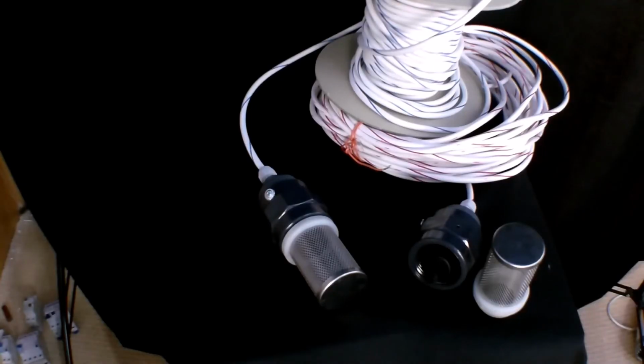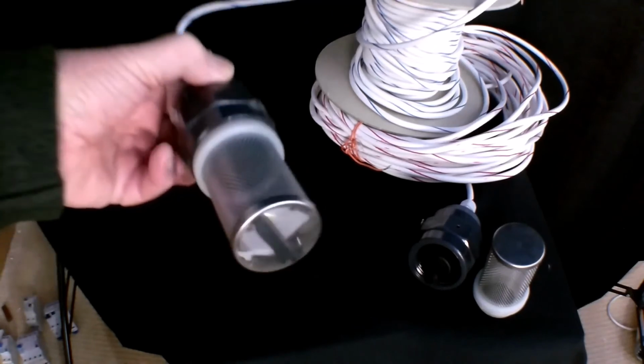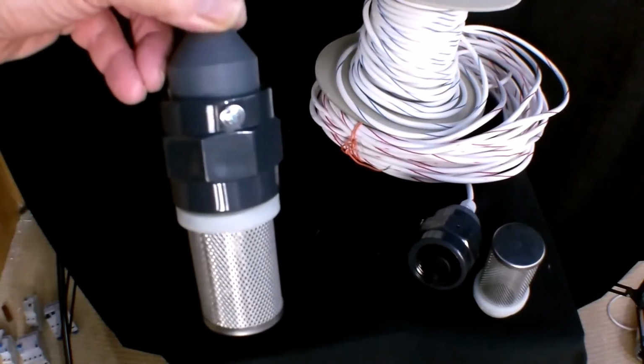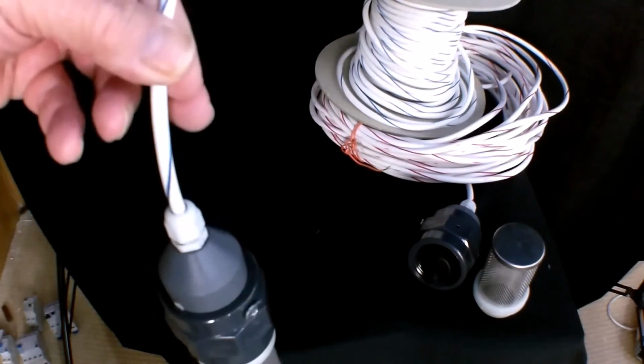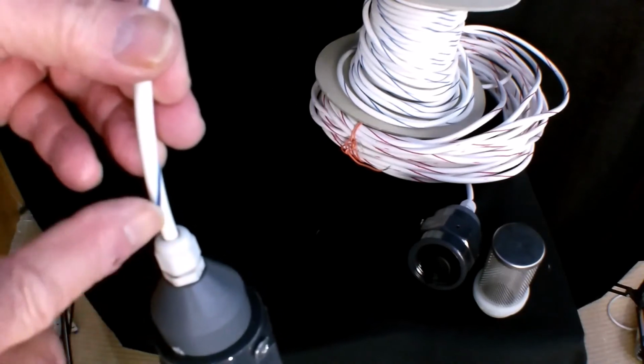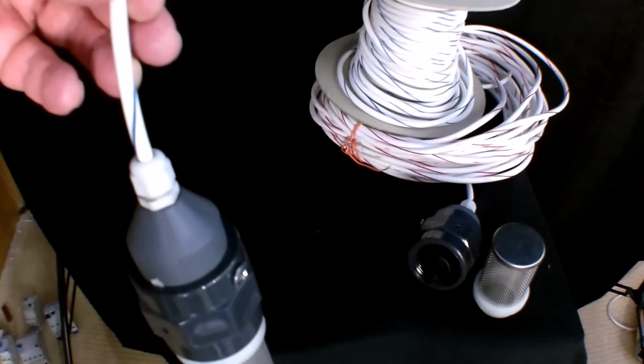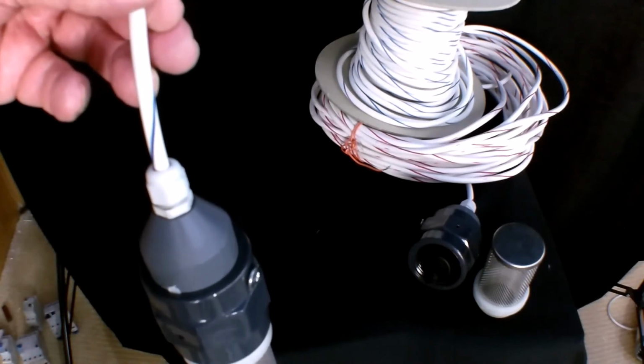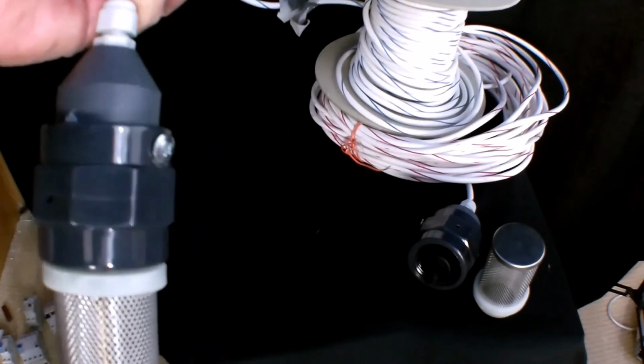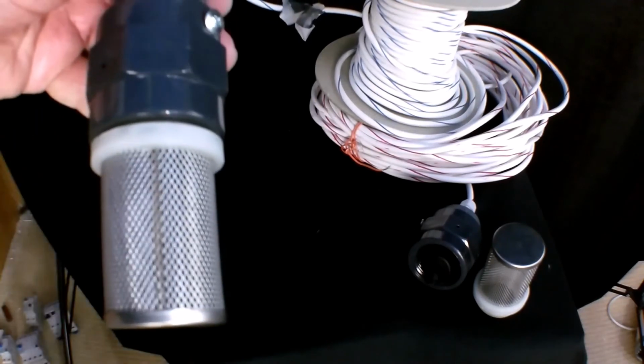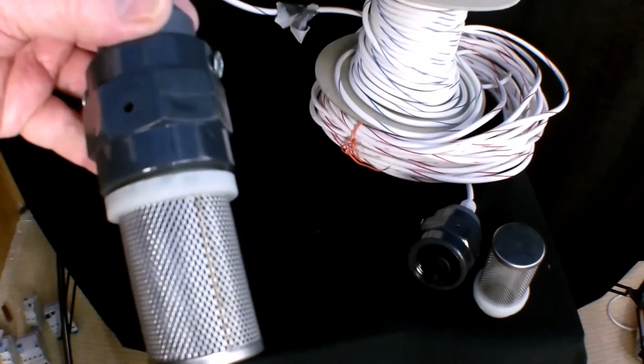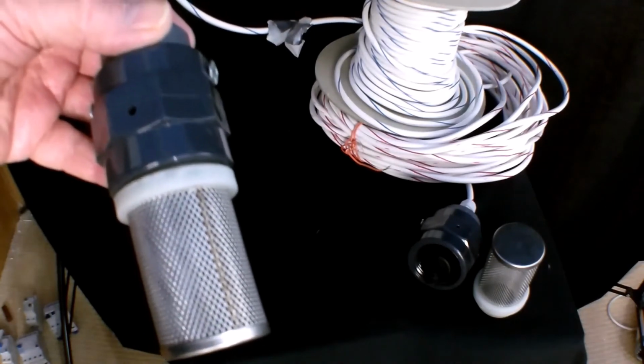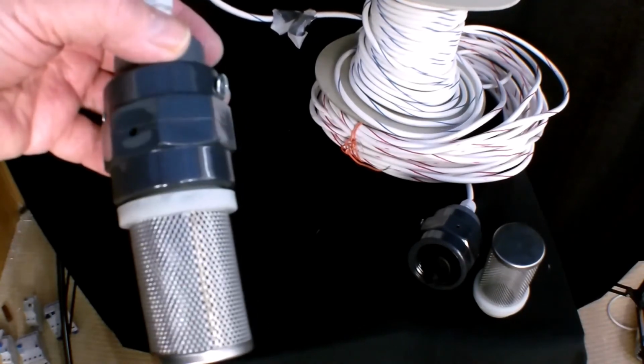Now these are some of the float switches that we manufacture. Here you can see it in its normal suspended position. There's a colour tracer that runs up the side of the cable. We use 4 different colours, white and black, so if you've got up to 6 switches from a distance, you know which one it is that you're working on at the end of the cable. Dead easy to get them mixed up.